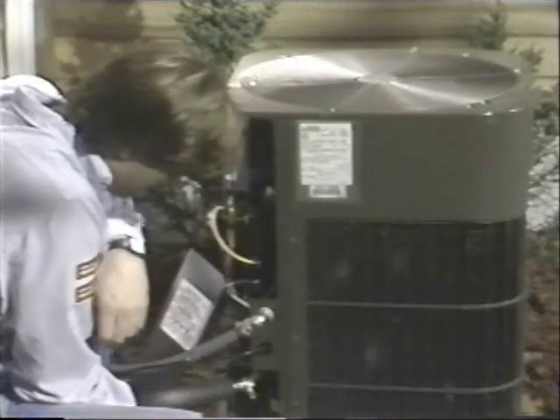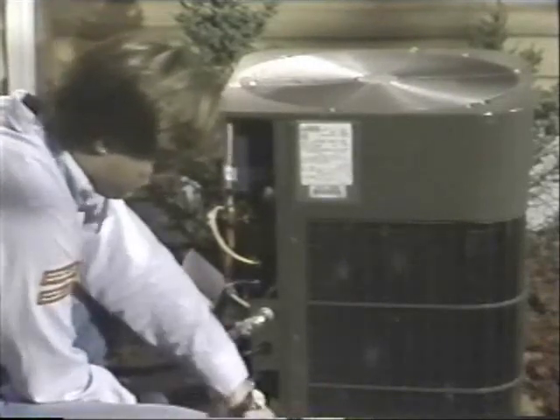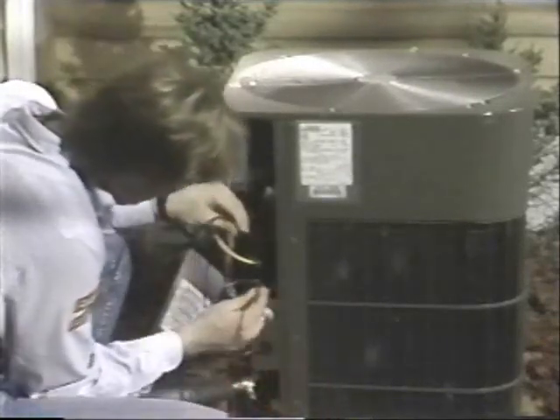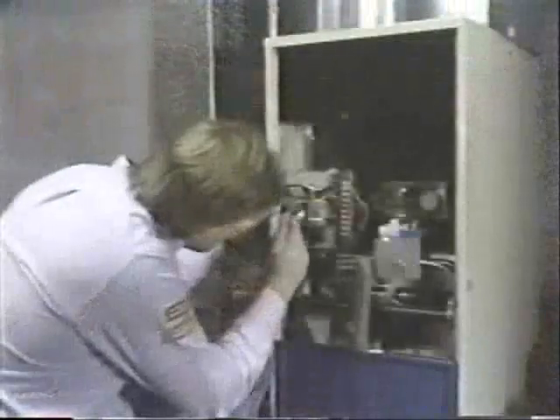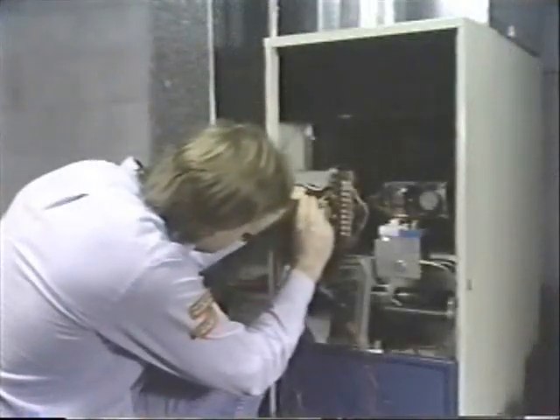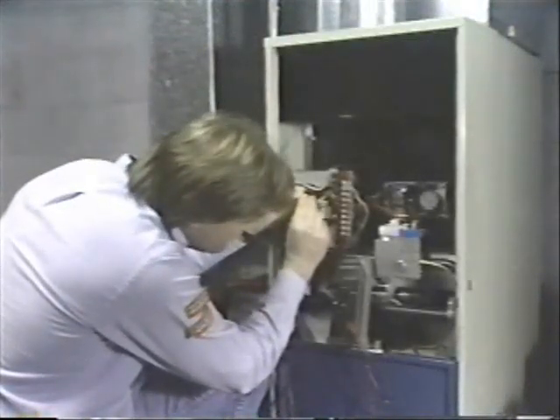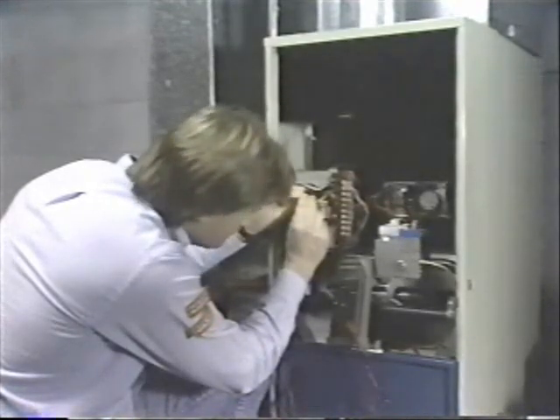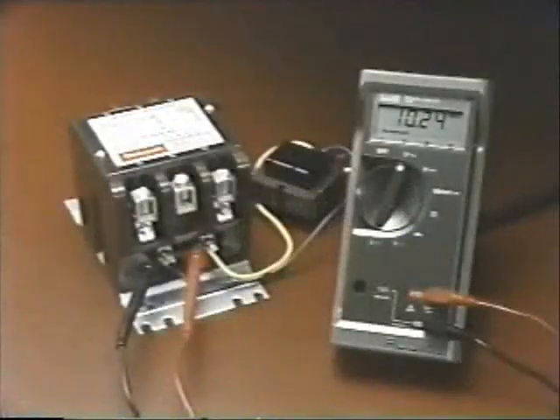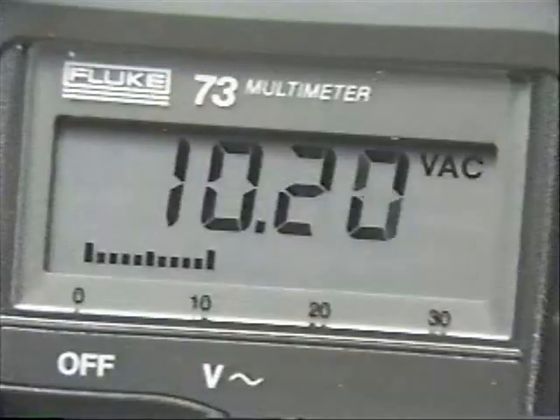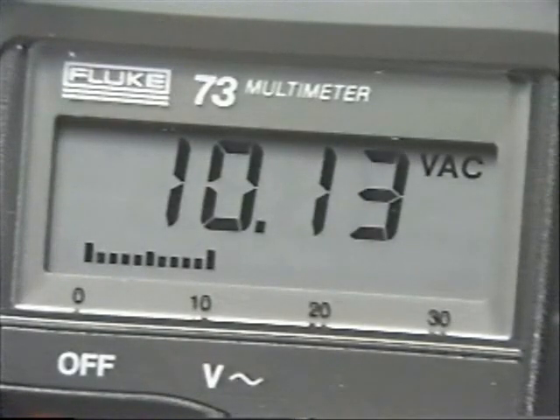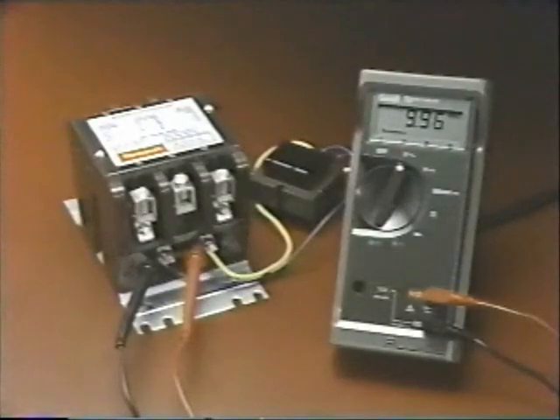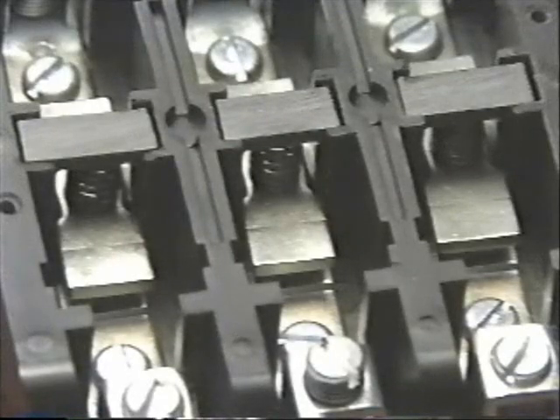If the contactor groans or hums but won't pull in, low voltage may be the problem. Check for an undersized transformer and/or low voltage at the primary side of the transformer. Supplying abnormally low voltage to the control circuit can cause chattering or sticking contacts, burned out coils, or improperly closed contacts.